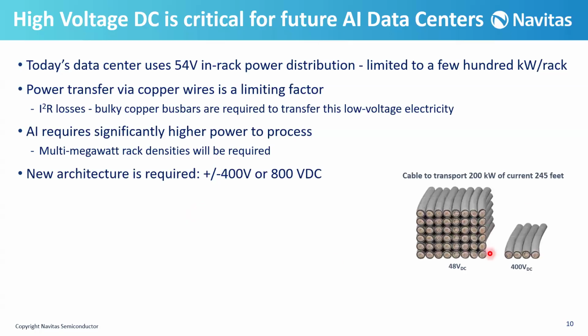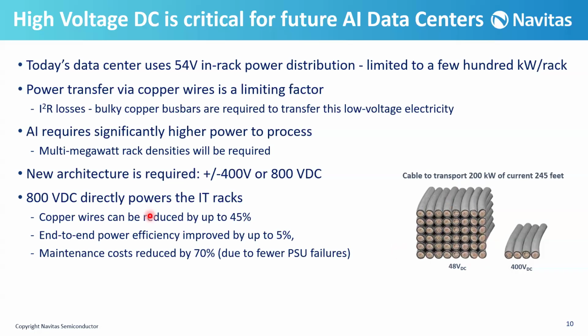As a comparison, here you can see the cable needed to transport 200 kilowatts of power. This is for 48 volt DC. And if we increase the voltage to 400 volt DC instead of 48 volt, obviously we need smaller cables, less copper. So it means that we have lower power loss, the first item. And the second one, we have lighter weight and lower cost. And finally, 800 volt DC directly powers the IT racks. It means that the copper wires can be reduced by up to 45%, as I explained here. End-to-end power efficiency improves by up to 5%, and maintenance costs are reduced by 70%. And the reason is we have fewer PSU failures.